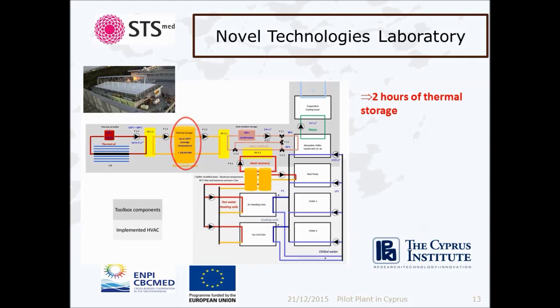This permits so to store at higher temperature and to shift the production even during the night by the creation of a higher temperature difference between the thermal storage and the temperature required by the system. For instance, at the Cyprus Institute, the heat is stored at 140 degrees and the absorption chiller requires only 88 degrees. The size of thermal storage reduces as a consequence. Also, thanks to the use of high temperature, double effect or triple effect chillers with higher COP, higher than 1, can be used. The heat is then transferred to heat medium loop for the absorption chiller.